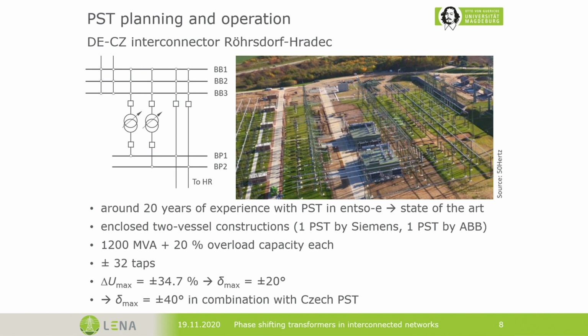You can see in this case we used a PST type that has been installed a couple of times before. It's a so-called Diele type. It's a two-vessel construction, and it has a rated power of 1,200 MVA with 20% overload capacity. We have 65 taps, 32 in each direction, and these transformers each can produce a phase difference from 10 to 20 degrees. And we decided to place one of these PSTs on each line on the German part of the border, and the second PST on the Czech side of the border.